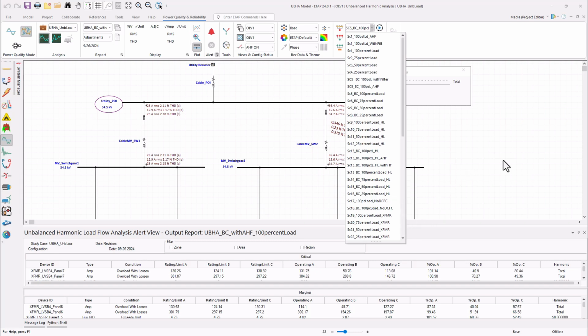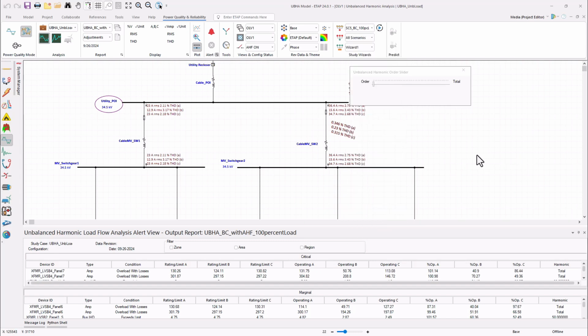Libraries were created by extracting the data from dynamic charging cycles of the DC fast chargers. And the evaluation was performed to identify percentage total current and voltage harmonic distortions at the point of common coupling and other locations. And those locations where the results were exceeding the limits were identified. And possible solutions such as installation of active harmonic filters at the switchboard level was recommended to deal with the excessive voltage distortion that was noticed in some locations.